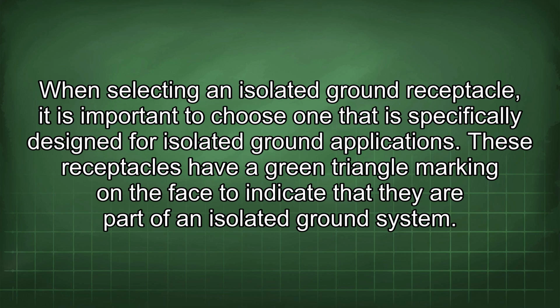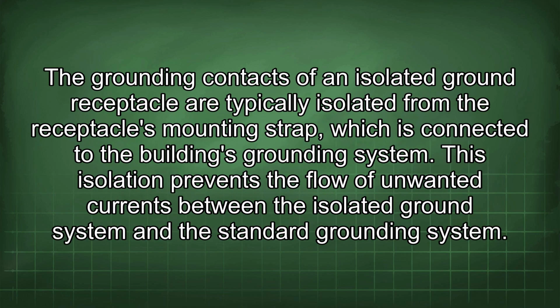When selecting an isolated ground receptacle, it is important to choose one that is specifically designed for isolated ground applications. These receptacles have a green triangle marking on the face to indicate that they are part of an isolated ground system. The grounding contacts of an isolated ground receptacle are typically isolated from the receptacle's mounting strap, which is connected to the building's grounding system. This isolation prevents the flow of unwanted currents between the isolated ground system and the standard grounding system.